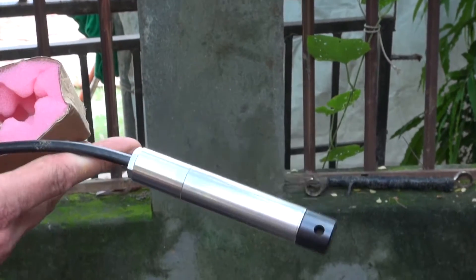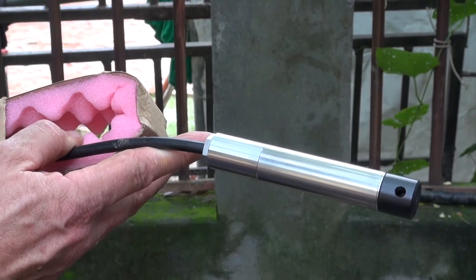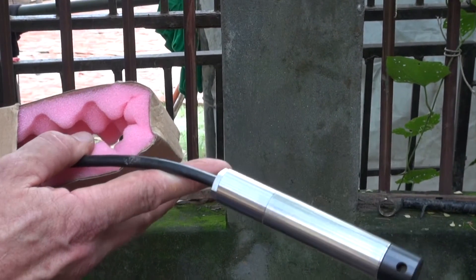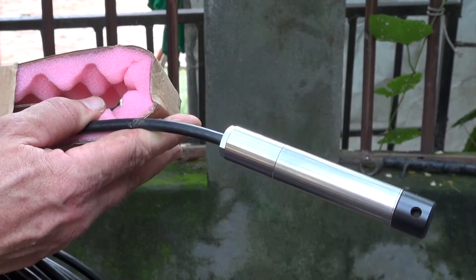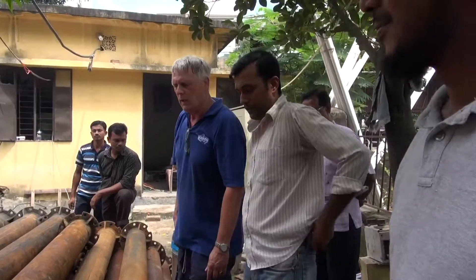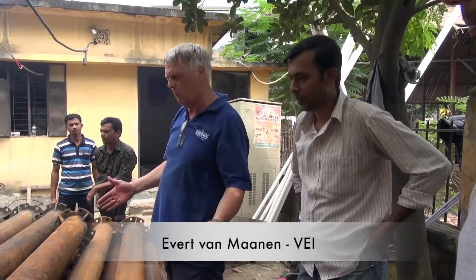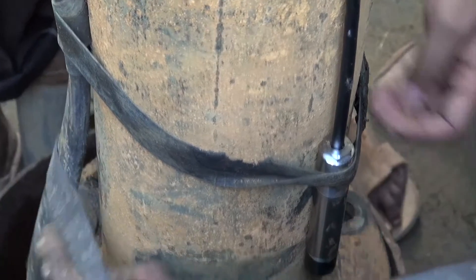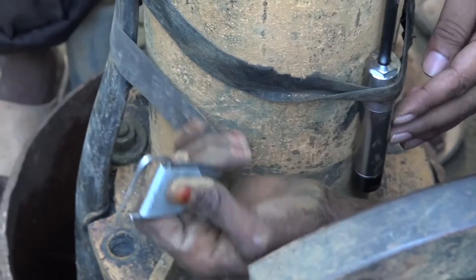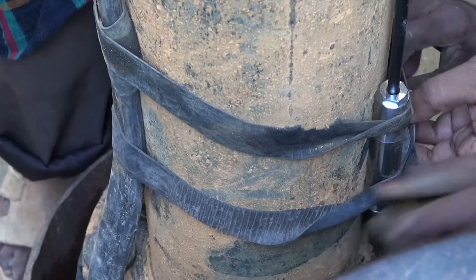This is the level transmitter that is connected to the pipe. When the pipe is lowered into the ground, it will be below the water surface, and it will measure the level of the water surface above the pump. Normally the water level will be around ten meters above the motor. We placed the water transmitter on the lowest pipe, so it will measure about ten meters of water surface above the level.